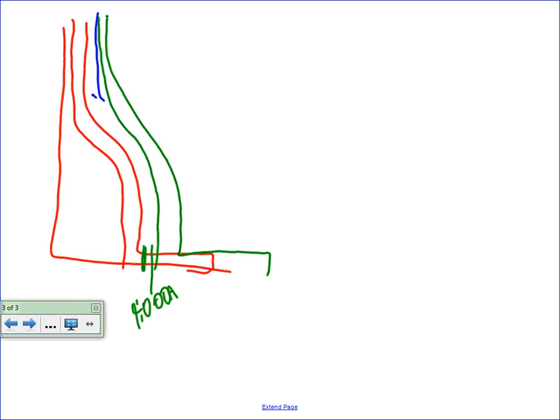And then there's the short time portion of that breaker. And the short time is anywhere from 2 times the handle rating of the breaker to 6 times the handle rating of the breaker. And we call it the short time because it covers the mid portion of the curve, and we can adjust this part of the curve up, or we can adjust it this way. So now we have full control of that curve. We can move it this way, we can move it up and down, we can move it left and right.